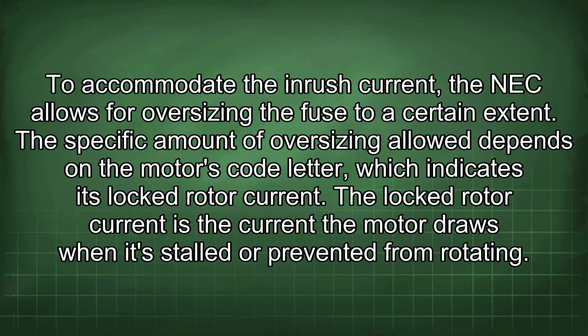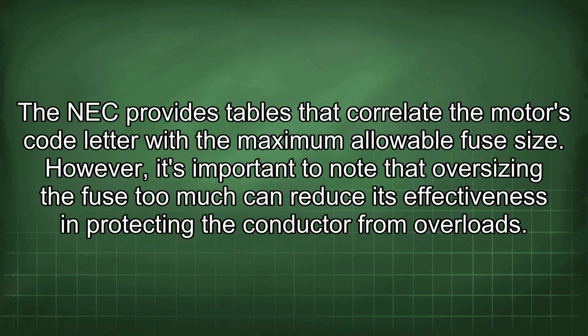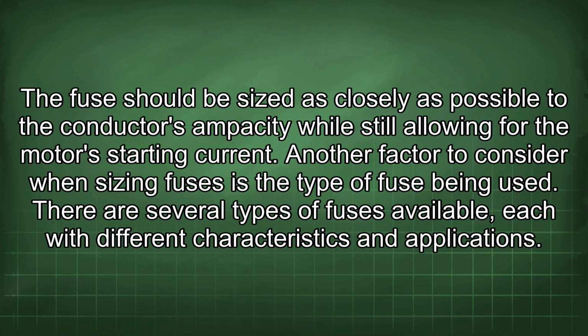The specific amount of oversizing allowed depends on the motor's code letter, which indicates its locked rotor current. The locked rotor current is the current the motor draws when it's stalled or prevented from rotating. The NEC provides tables that correlate the motor's code letter with the maximum allowable fuse size. However, it's important to note that oversizing the fuse too much can reduce its effectiveness in protecting the conductor from overloads. The fuse should be sized as closely as possible to the conductor's ampacity while still allowing for the motor's starting current. Another factor to consider when sizing fuses is the type of fuse being used.